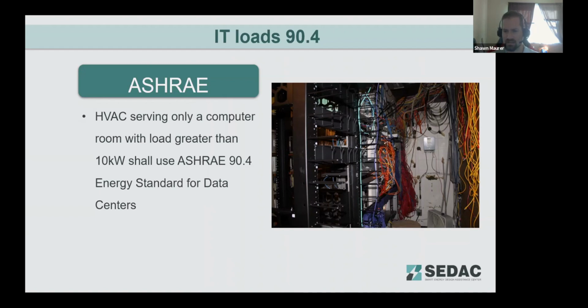It's good to understand where the threshold is between a room with IT equipment and a data center. Buildings commonly have several IT equipment rooms that contain equipment such as switches and servers, but those would not be considered data centers. This is specific to data centers. And again, it's that equipment load greater than 10 kilowatts.